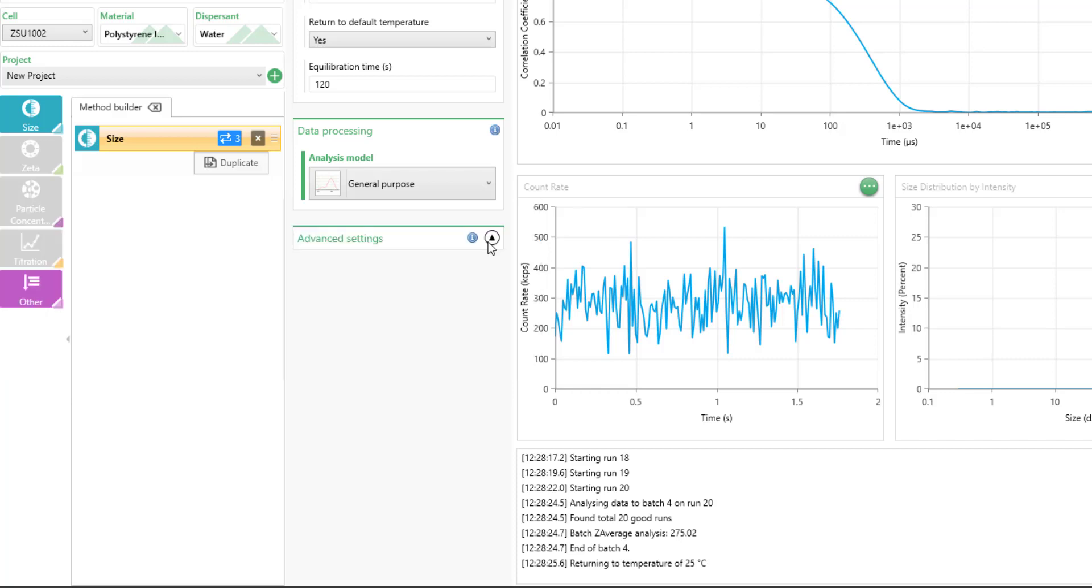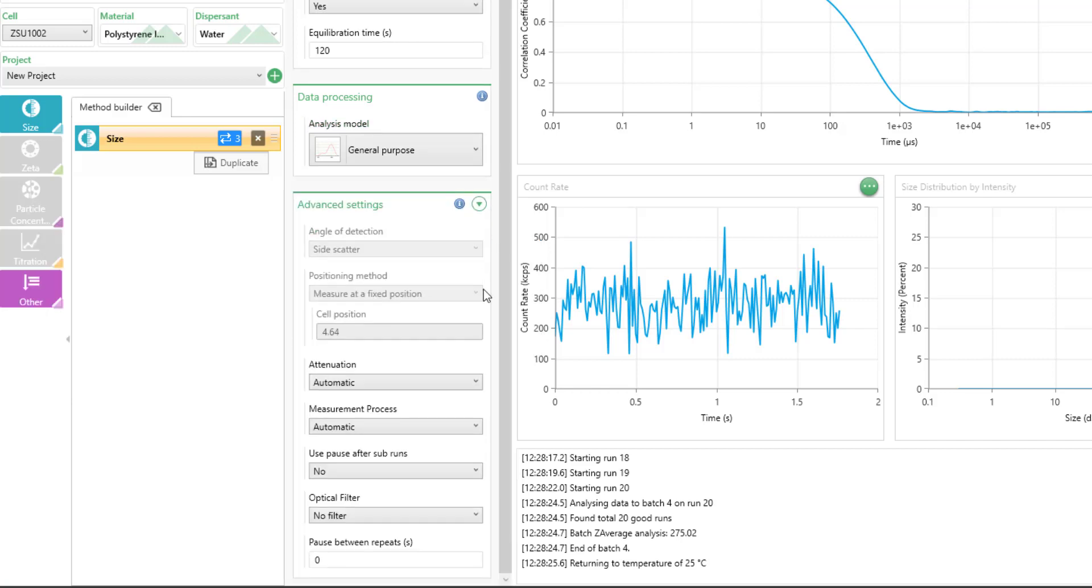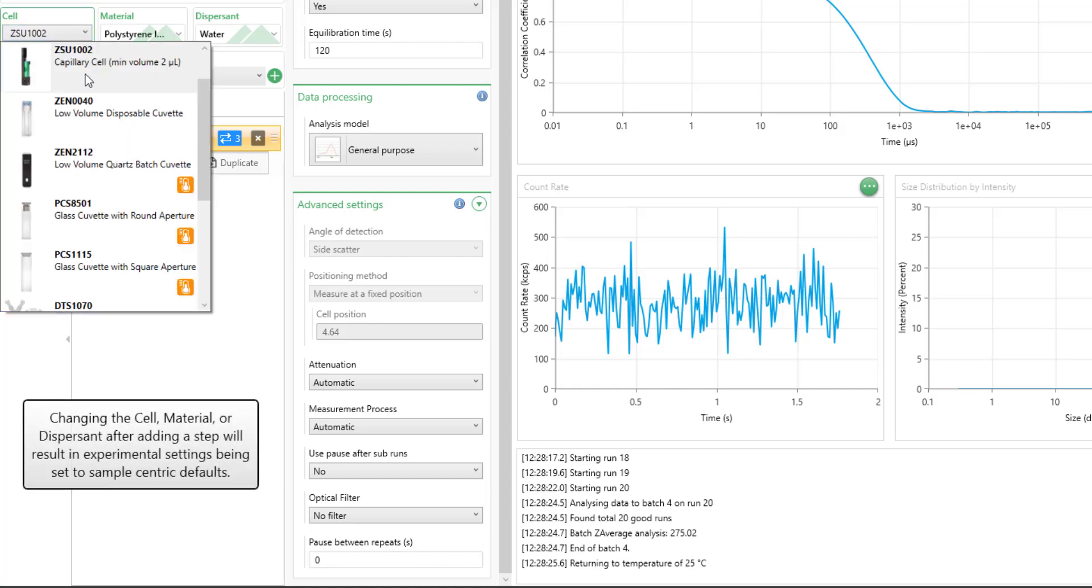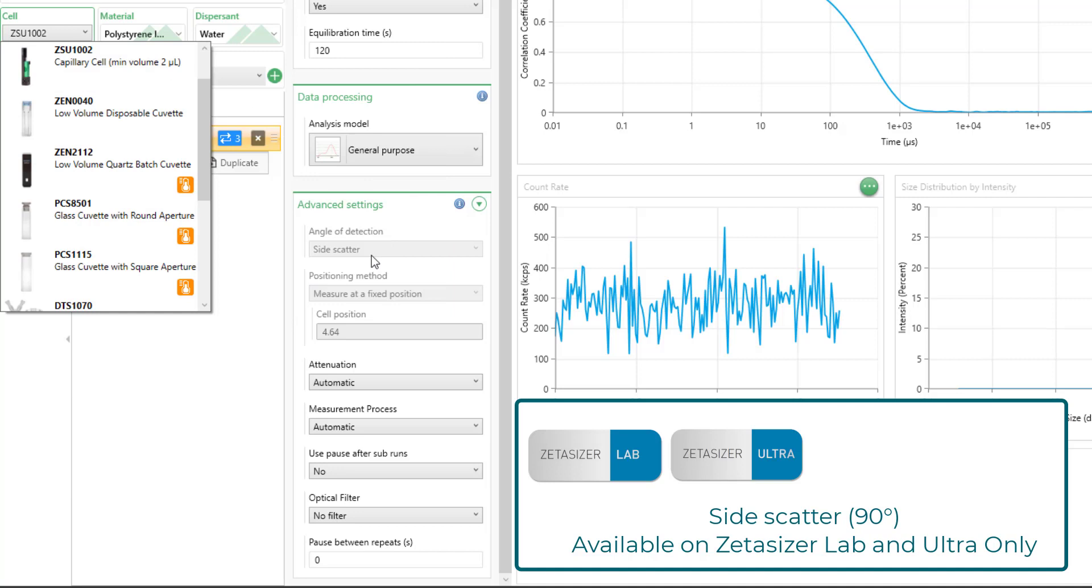On the advanced settings, this is where you can change the scattering angle that you'd like to measure at, depending on the type of cell that you have selected here. For example, right now I have this special capillary cell selected that can only be used at 90 degrees or side scattering, so the instrument won't allow me to change the measurement angle. However...